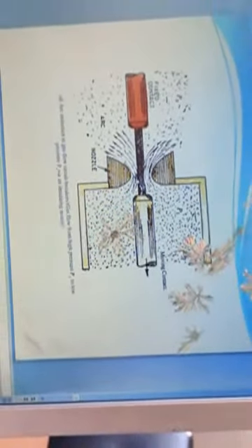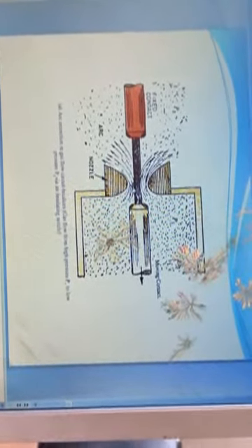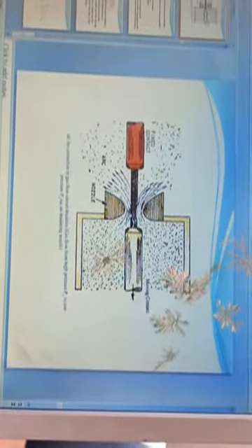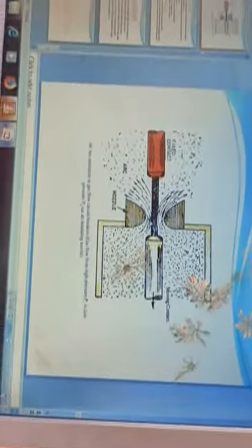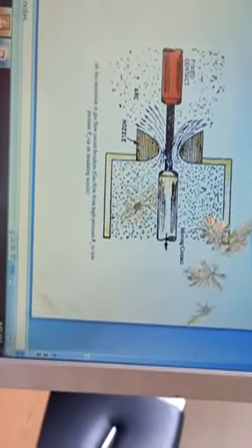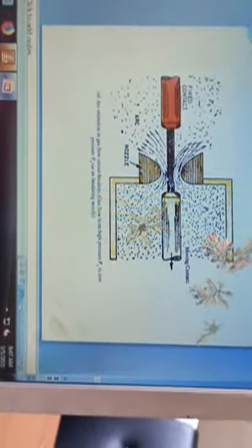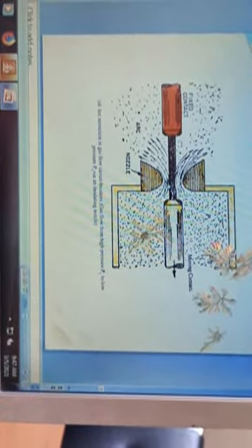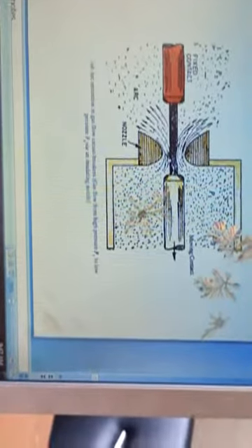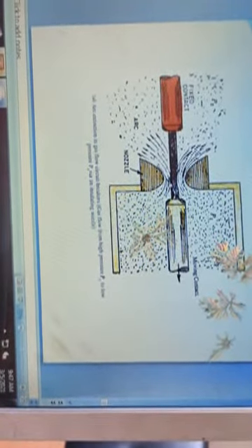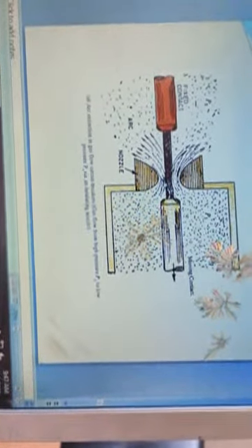The diagram shows the next circuit breaker, that is the SF6, sulfur hexafluoride, circuit breaker. SF6 is an inert heavy gas having good dielectric and arc extinguishing properties. Its physical properties are: colorless, odorless and non-toxic. Pure SF6 gas is not harmful to health.